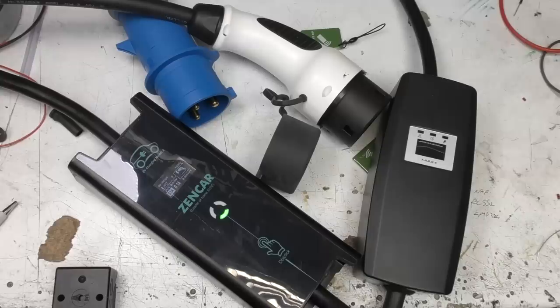There are some minor issues with the diode check. Now, in terms of safety, I think it's a pretty small window of potential problems there. Basically, in order for that to be an issue, you'd have to have some sort of fault on the cable or the plug, which put a low enough resistance on the pilot signal to get it to turn on, but not so low that it produces a fault indication.